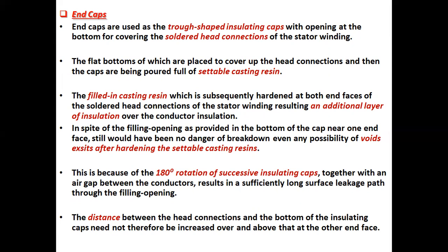This is because of the 180-degree rotation of successive insulating caps, together with an air gap between the conductors, which results in a sufficiently long surface leakage path through the filling opening. The distance between the head connections and the bottom of the insulating caps therefore need not be increased over and above that at the other end face.